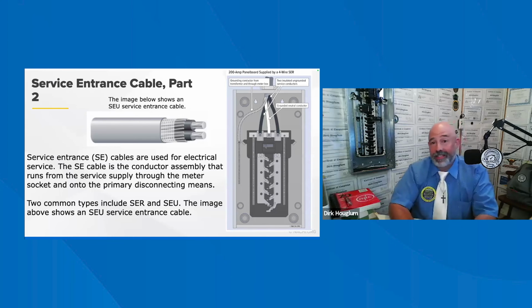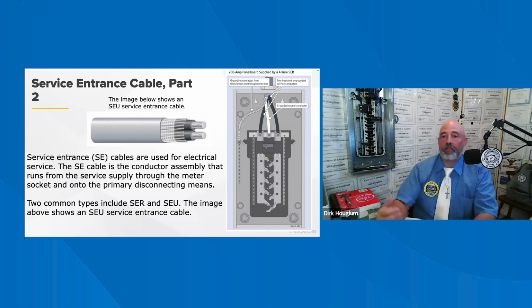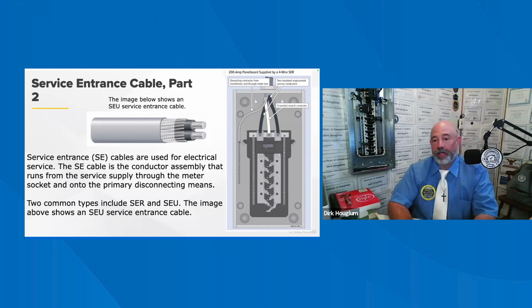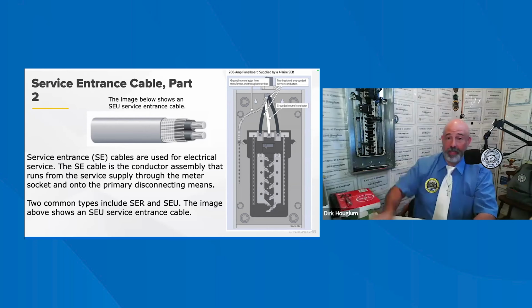In most homes, SE cables carry power from the service drop to the meter, then from the meter to the main panel. The example shown is a 200 amp panel fed by a 4-wire SER cable, where the main disconnect is located outside of the meter and another disconnect is installed inside the panel.